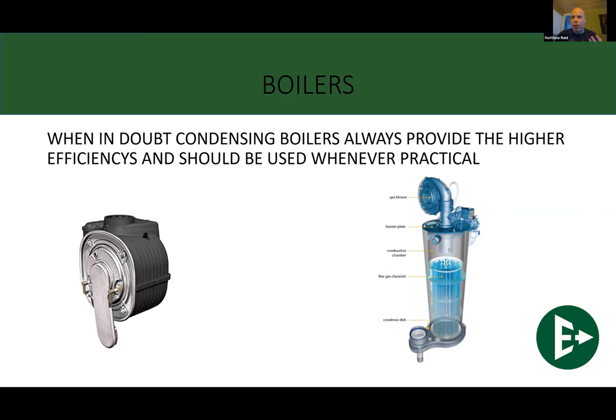The reason why it was billed as self-cleaning is because as it sweats, the condensate runs down inside the unit, in theory giving it a wash, even though it's just not technically true. It does do something for it, but definitely not enough to classify it as clean. And plus, if you're burning propane through either of these, propane is super dirty. I don't care where you're getting it from, whether it's the top of the propane tank or the bottom, it's still a dirtier fuel. So you still need to make sure you get these jackets cleaned out.